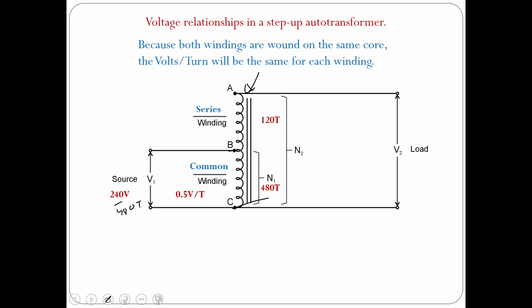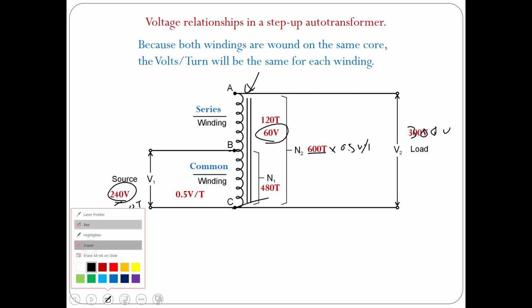So if I had 120 turns on the series winding and a total combined 600 turns, we could determine the voltages. So 120 turns times 0.5 of a volt per turn gives you 60 volts. And if we add these two voltages, 240 plus 60, that's going to give us 300 volts. Or we could look at 600 turns times half a volt per turn. Total is also 300 volts. All right. So 300 volts.